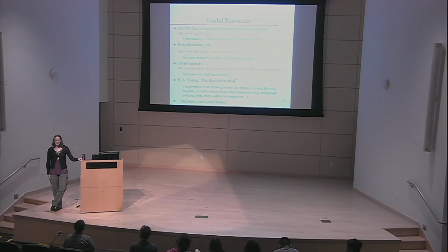The best thing you can do is make sure your instrument is well aligned with an external standard, okay? And just bug the people who are responsible for it until it is well aligned if necessary, because then you know that you don't have to worry about a zero point, and you know that any errors would come from some height offset of how the film is mounted, things like that.